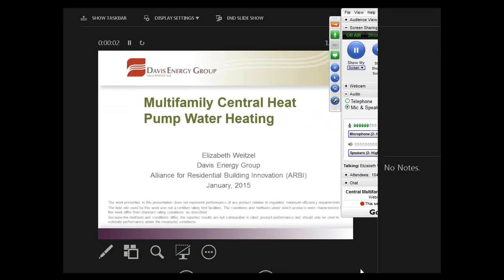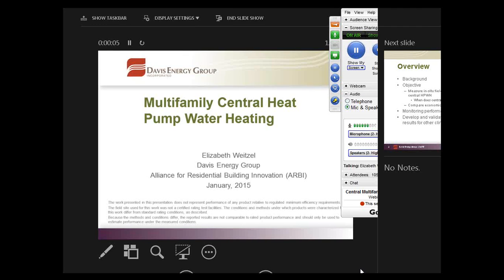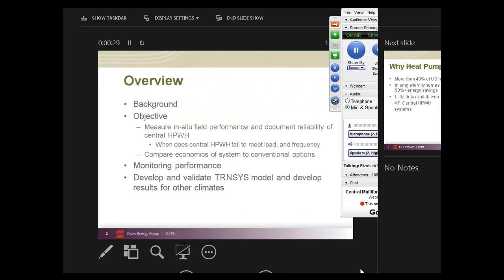So today I'll be sharing the results of a field evaluation of a 10.5-ton heat pump water heater that was installed at the University of California, Davis's West Village student housing. But before I go any further, I just want to add the disclaimer that the results presented are not representative of certified rated testing conditions, that they are field performance data, and the conditions in operation are different than those used for performance standards. So with that in mind, we'll continue on.